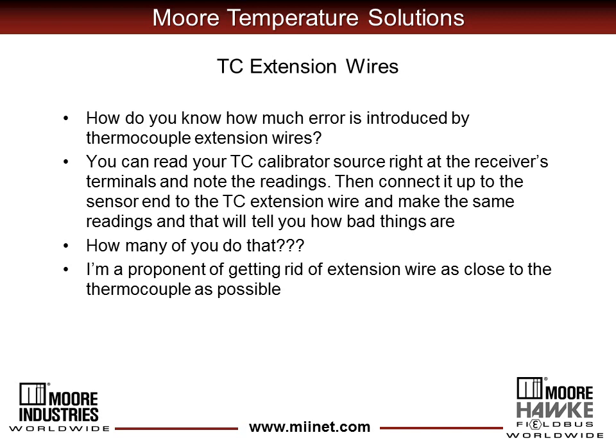Do you check to see how much error is caused by thermocouple extension wire? Most people I know ignore the entire subject until operations calls up and declares that this temperature measurement is a problem, or perhaps there's a catastrophic measurement failure. We all know thermocouples fail, but thermocouple extension wire also fails. When it does, it has to be replaced. If you replace the extension wire with new extension wire, you're just reintroducing the error it causes — you're simply perpetuating the same problems. You may have to live with thermocouples, but you don't have to live with thermocouple extension wire. I'm a big proponent of replacing it with other technology.